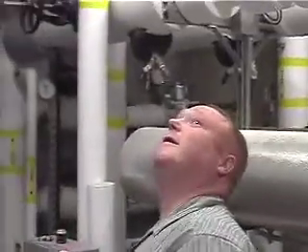Where are the chilled water flow sensors? Chilled water flow sensor is, I think it's in there. There it is. Those have to be serviced every year, I believe. In a clean system like what you have here, I think they're okay. In a condenser water system where it's open atmosphere and you get some stuff, you would want to service those about once a year. It's a turbine. It's got a little turbine in it, very fine. So if you get a lot of debris in it, if you have a dirty system, you will have to service it.